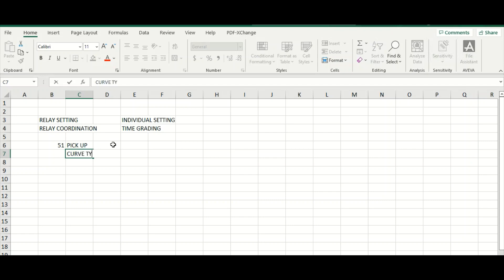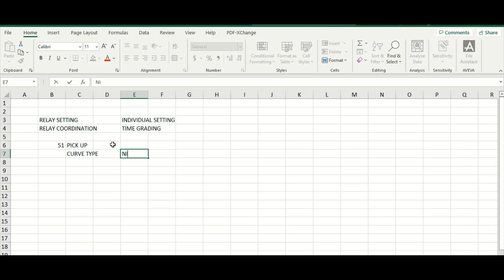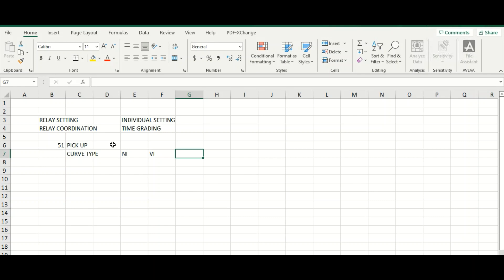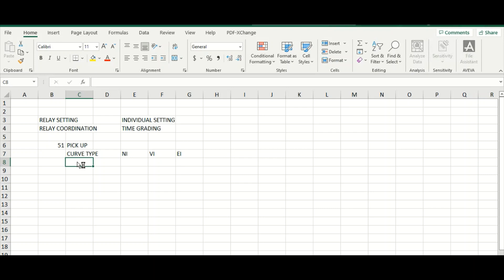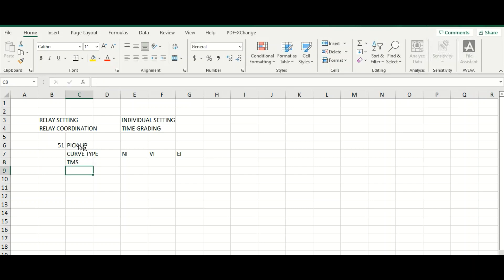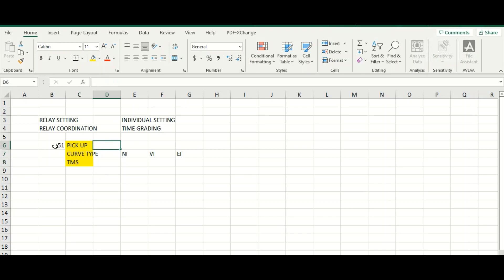One is relay pickup, which means relay pickup current. Then curve type, which curve. Suppose which IEC curve you are going to choose, whether it is IEC normal inverse, very inverse, or extremely inverse. And the third thing is the TMS, the time multiplier setting. So these three inputs you need to provide as the relay input for 51 element.